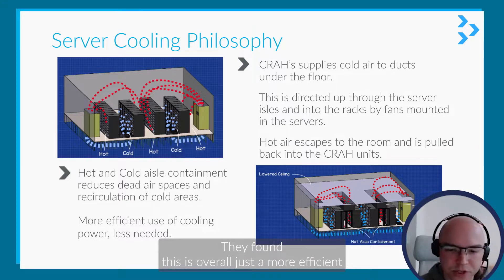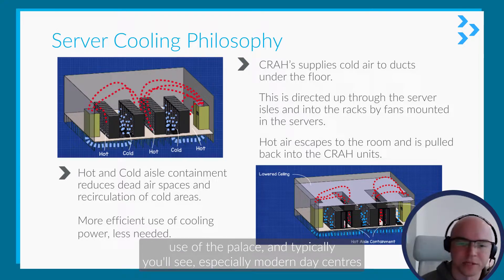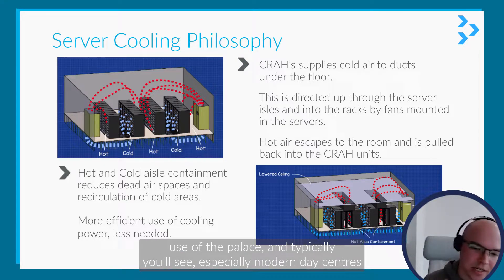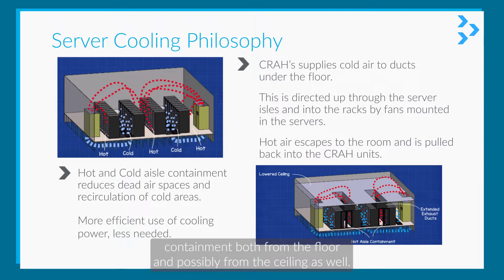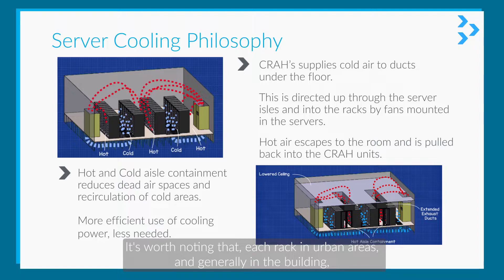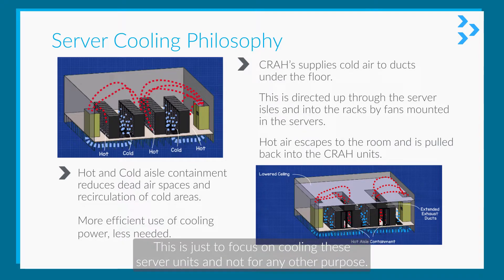This is overall just a more efficient use of power, so typically in modern data centers you'll see containment both from the floor and possibly from the ceiling as well. It's worth noting that HVAC in admin areas and generally in the building is done separately, with separate air handling units — this is just focused on cooling the server units and not for any other purpose.